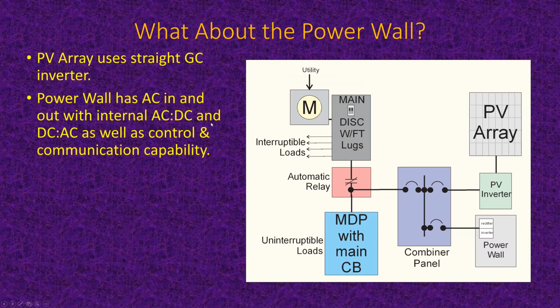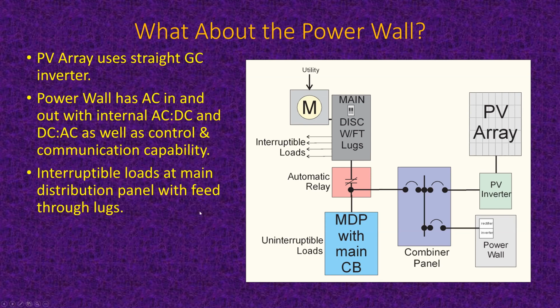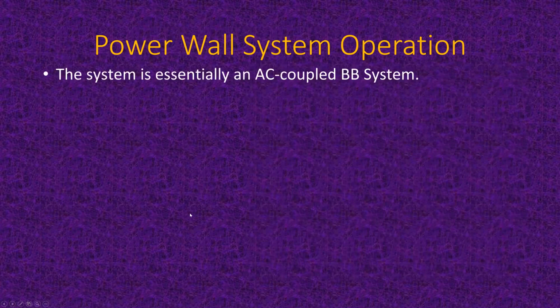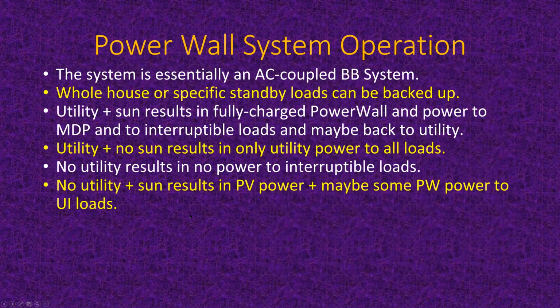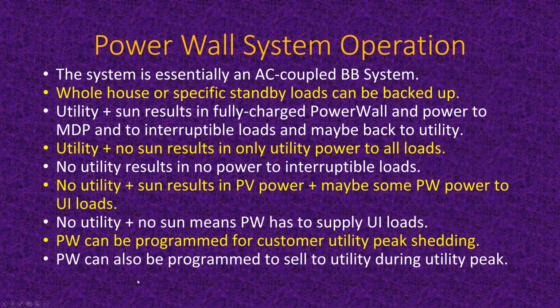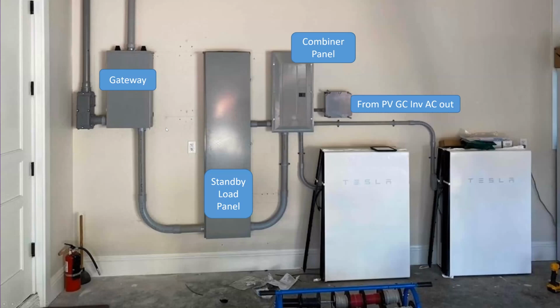Okay, there's our Powerwall. And here's what Powerwall has. And we pretty much talked about this stuff, okay? System operation, we pretty much talked about this. AC coupled system, same story. And here's that Powerwall system you saw on the very first slide. Now the covers are on. You can see that's the gateway in that box on the left, standby load panel, combiner panel. The PV is coming in from the wall from another place. And a couple of Tesla Powerwalls rated at about 13.5 kilowatt hours each. So we're looking at 27 kilowatt hours of storage here.